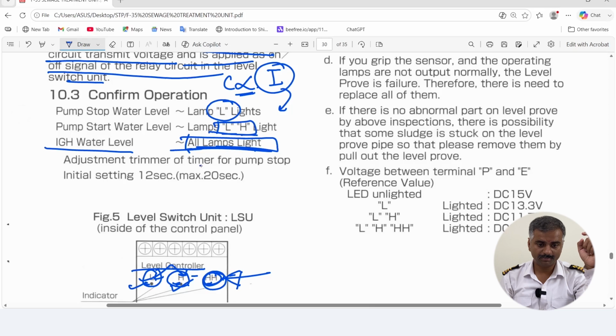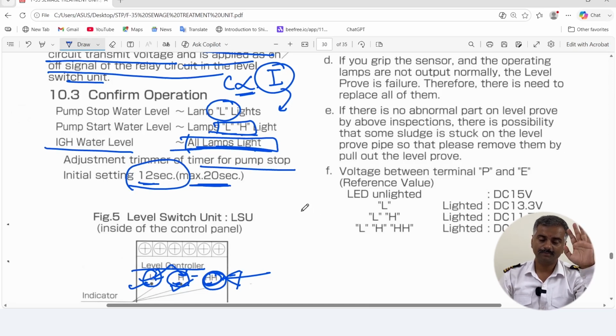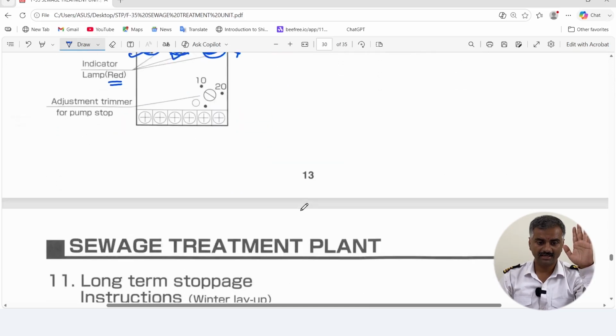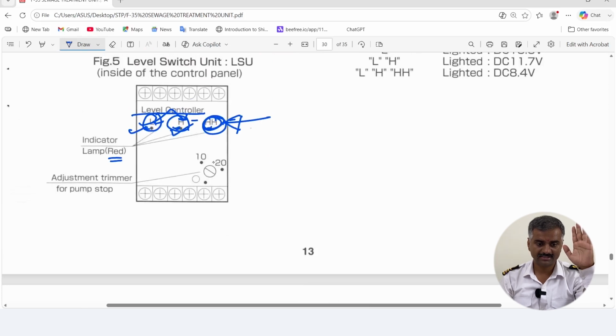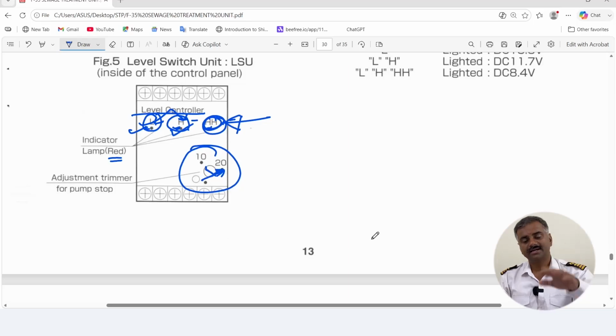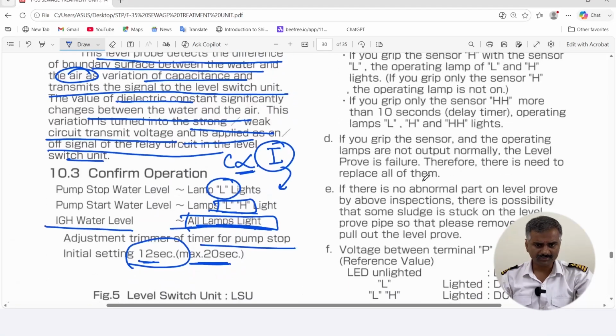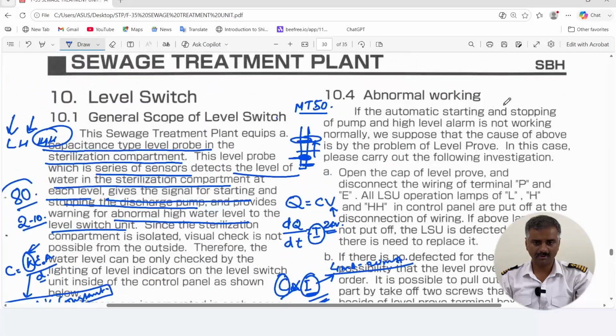And then there is a pump stop timer. Say they have set it initially at 12 seconds. You can change it to a maximum of 20 seconds. That much time only the pump will run, and then it will cut off. You have the adjustment timer inside the control panel. You open it like this. This is how the timer looks. This is set at 10 to 12 seconds. You can set it maximum up to 20 seconds. So that is the concept over here. In the next one we will read something more about abnormal working of the level switch. Thank you guys.